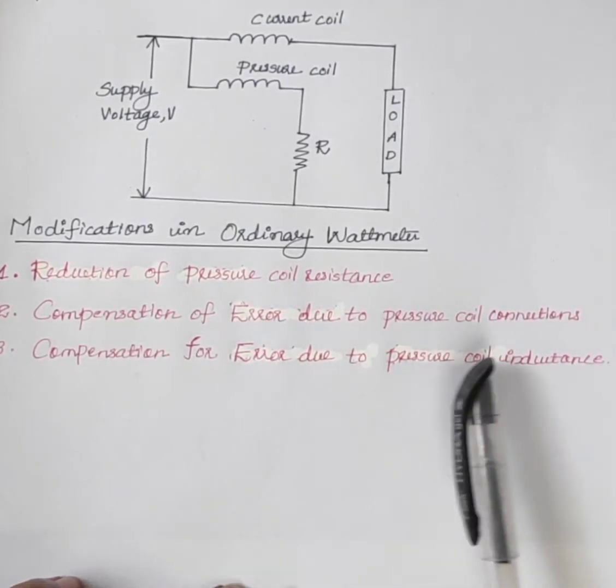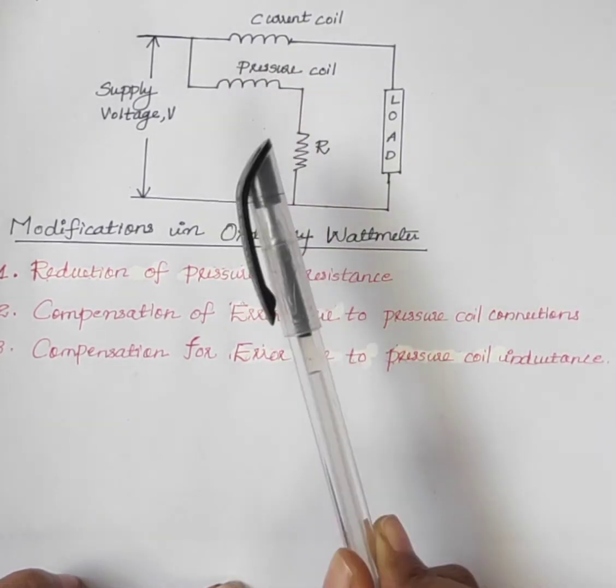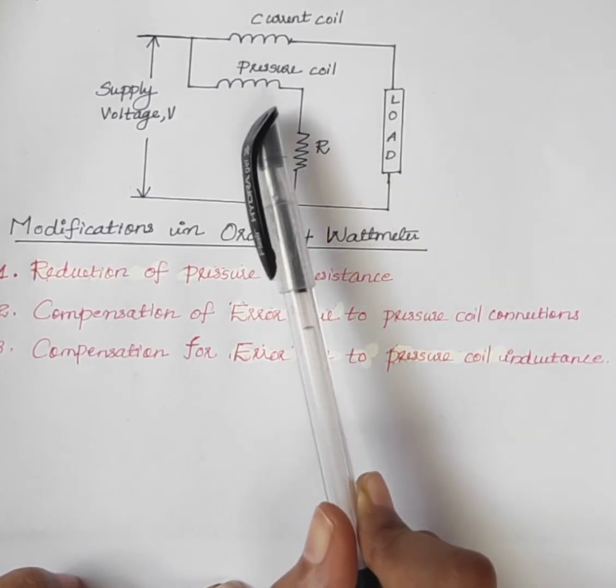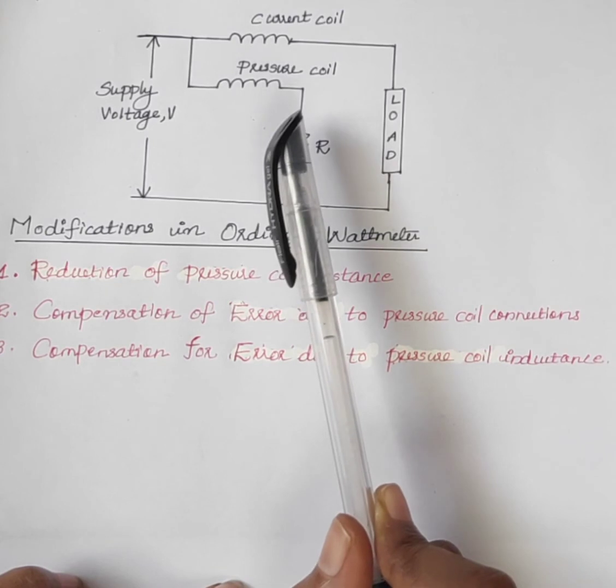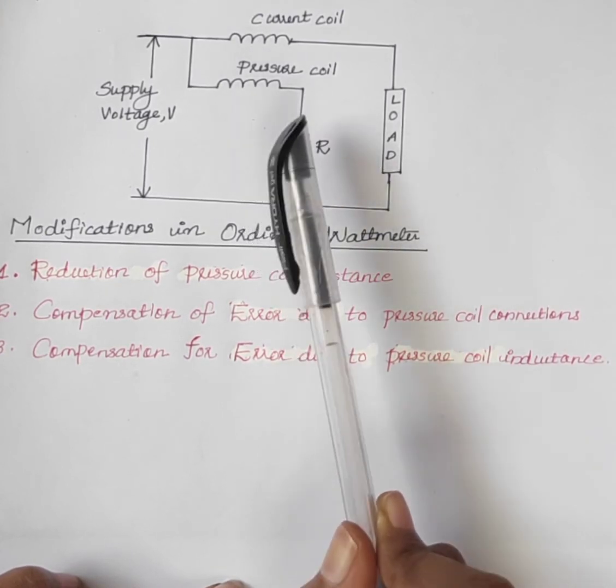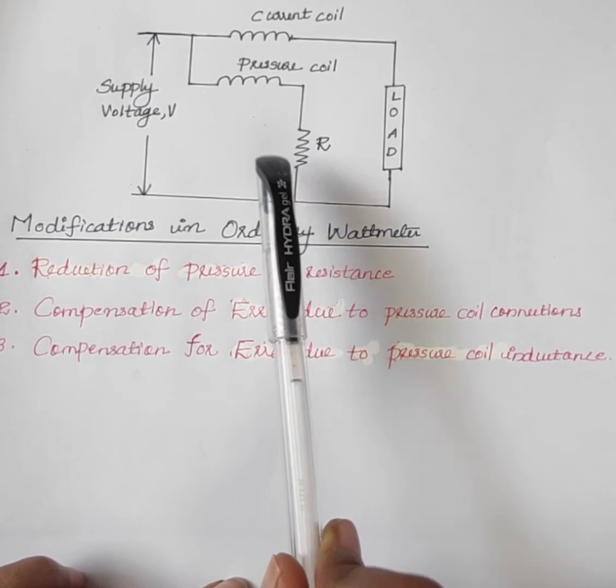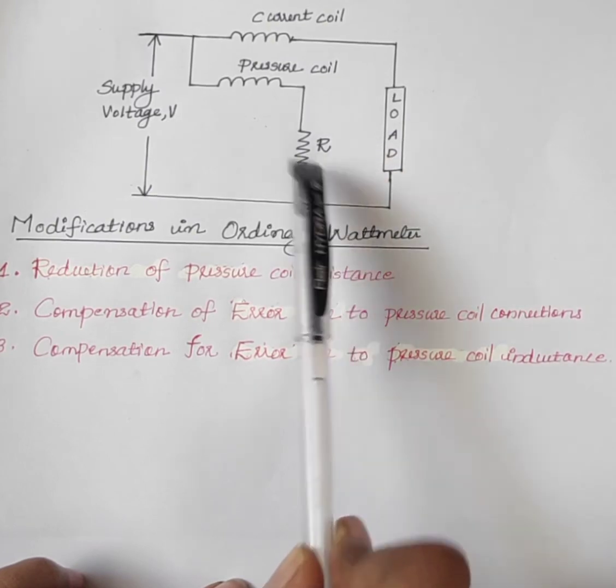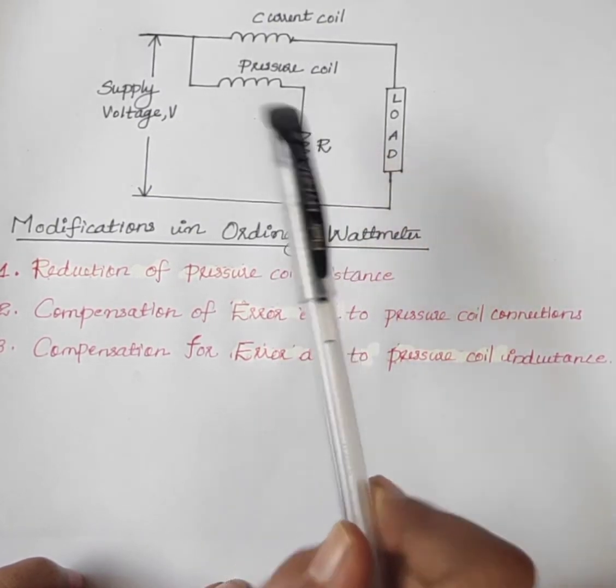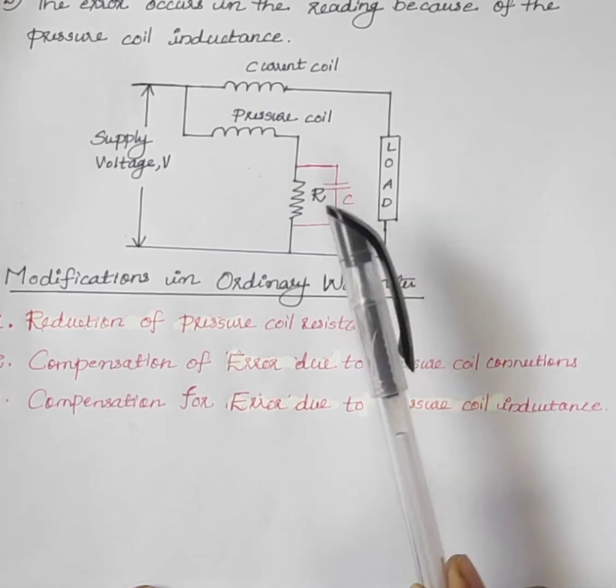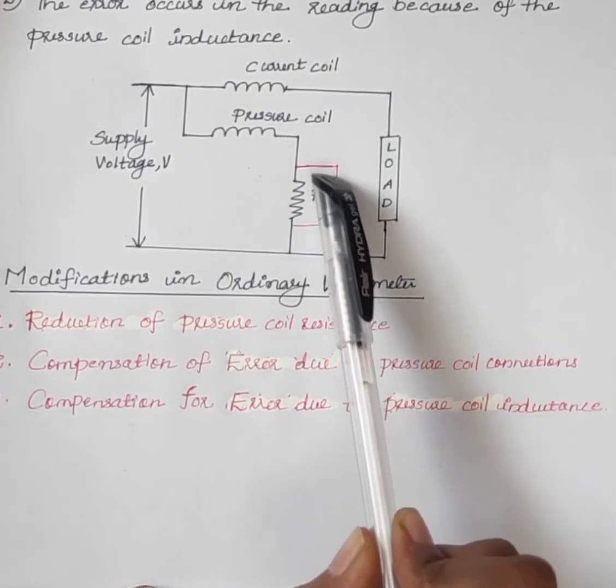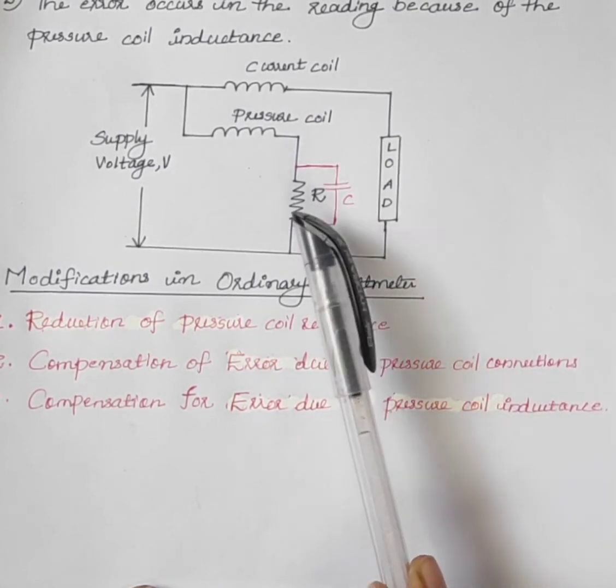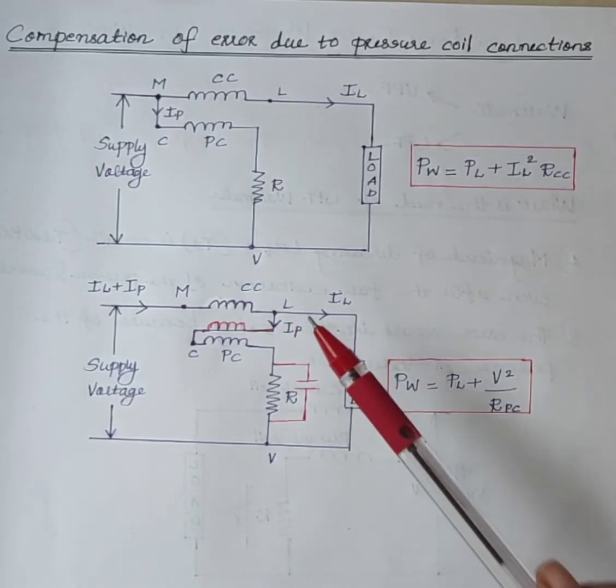The third modification is compensation of error due to pressure coil inductance. A small amount of inductance is present in the pressure coil of the watt meter, and this inductance causes error in the reading. This type of error can be reduced by connecting a capacitor in parallel with the pressure coil resistance, so that the capacitive reactance cancels out the inductive reactance of the pressure coil, making the pressure coil purely resistive.